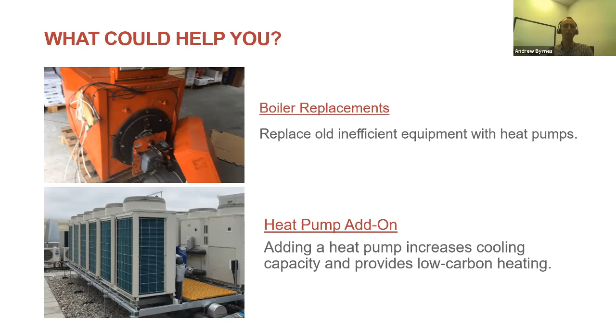Even if not doing a boiler replacement, a heat pump add-on can also be pursued to reduce carbon emissions from existing buildings. In many cases, an air to water or air to air heat pump can be integrated within an existing system to provide low carbon energy and reduce natural gas use, while maintaining the existing boiler as backup and peaking energy.